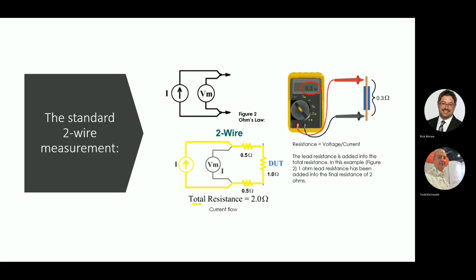So a two-wire is, well, as it states, it's two wires. Normally, if you have a digital voltmeter, you're going to have a black lead or a common lead, and then a red lead, which is the positive. If you were to measure the voltage on anything, you need two leads in order to measure the voltage, but the same goes for resistance. You need to have a connection loop around it with current flow. So if you're using a digital voltmeter, the actual current flow comes from the positive lead of the meter around to the negative lead of the meter, and then it calculates the actual resistance.